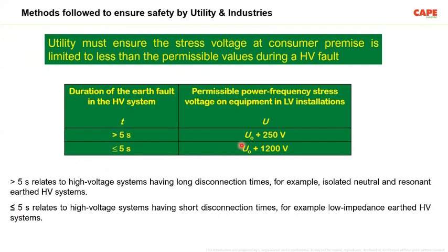Under that condition, the maximum overvoltage allowed inside a consumer premise must be limited to less than 1200 volt. More than 1200 volt, the utility shall not allow inside a consumer premise, because consumers have devices which cannot withstand such voltages. So it is the full responsibility of the energy supplier.